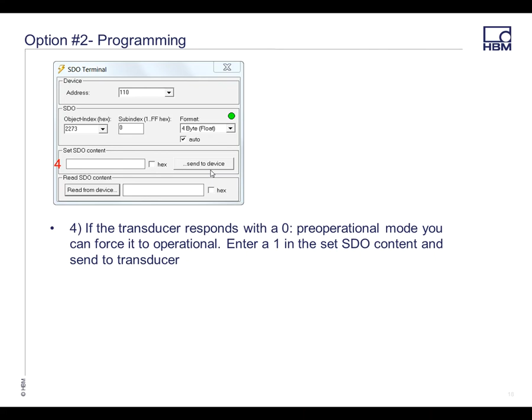After reading that, you want to send a command to the device telling it to broadcast all these codes. In the SDO content, which is the 4th step here, put a 1 in this field—don't check the hex box, just put a 1 in the box. Then select send to device, which forces it to send out the commands you had initially set up.